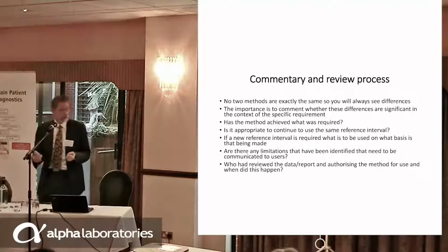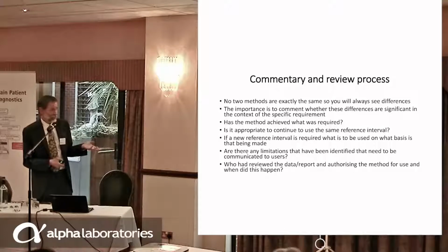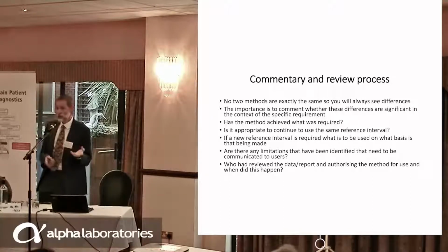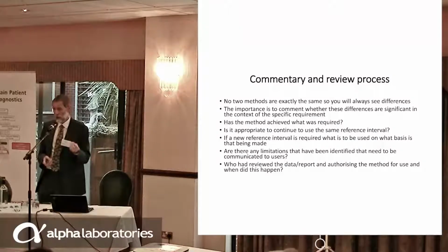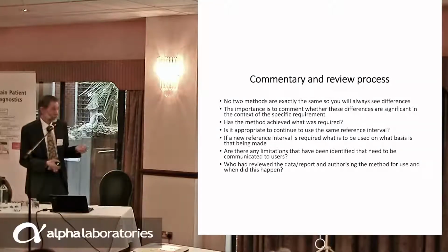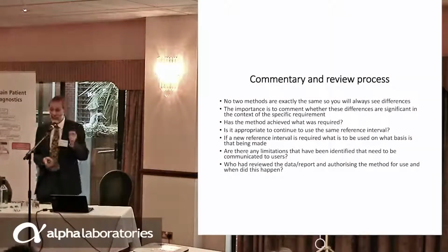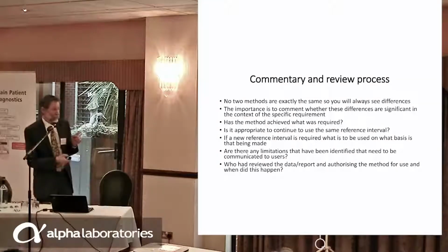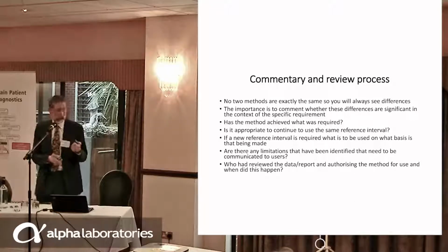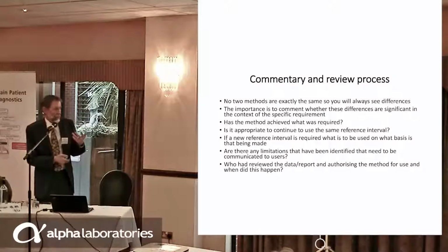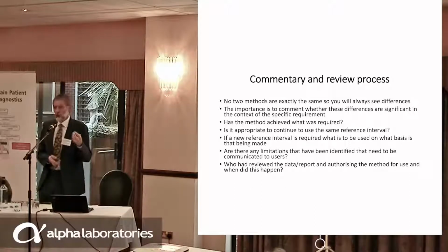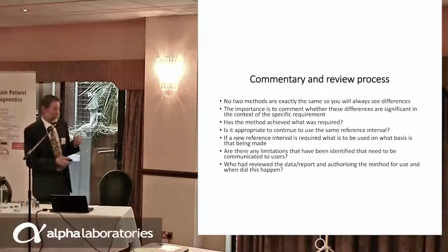Is it the manufacturer's? One of the things that I think has been very valuable is that none of us are going to do a comprehensive reference interval check for children, okay? We don't have the resources to do that. So looking at published data, so many of you I'm sure are familiar with the CALIPER study from Canada, where they've done a lot of reference interval work on children, and now with multiple different methods. And that's actually very helpful, I think, to try and look at your own data. When you've made your decision on your reference interval, make sure you document it in the verification.